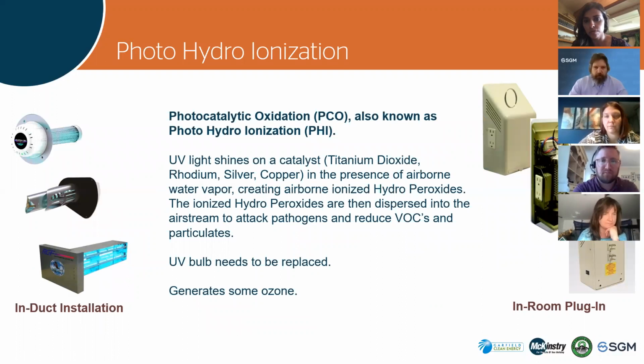Yes, the bottom line is yes, because this is more of a specialized one that it's UV light, of course, and then it is used with a catalyst, the titanium or silver, copper, etc. So it's a little different than just the ionizers that tend to produce ozone. Those are the ones that I warned about that are from your retail stores, the cheap little ones. So really look to see if they're UL listed to 867 or 2998. Okay.